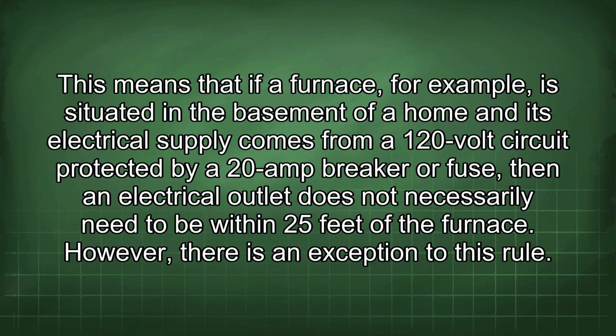This means that if a furnace, for example, is situated in the basement of a home and its electrical supply comes from a 120-volt circuit protected by a 20-amp breaker or fuse, then an electrical outlet does not necessarily need to be within 25 feet of the furnace.